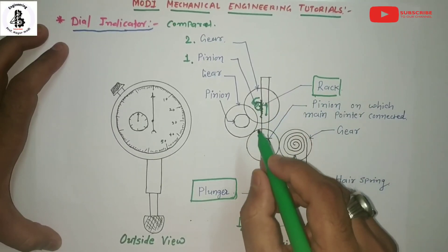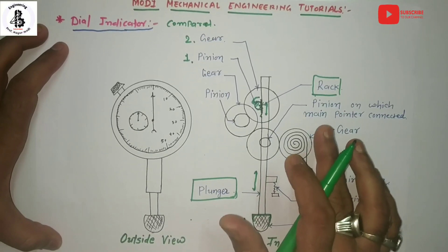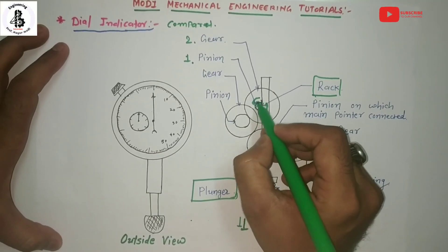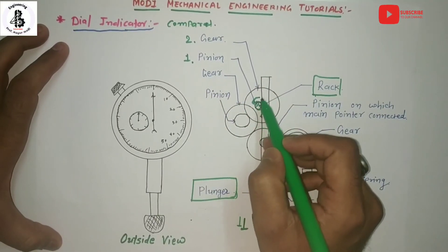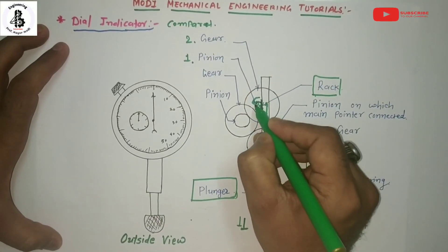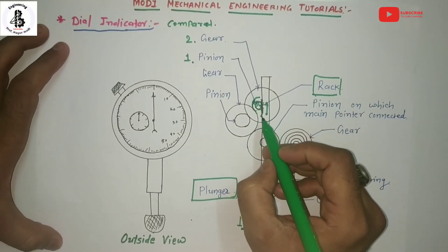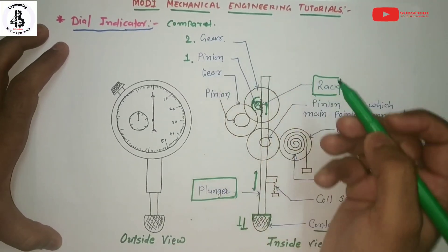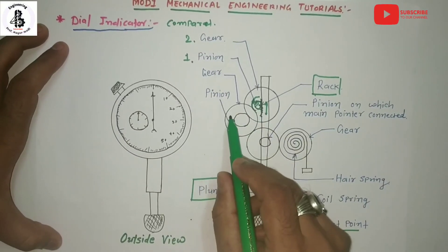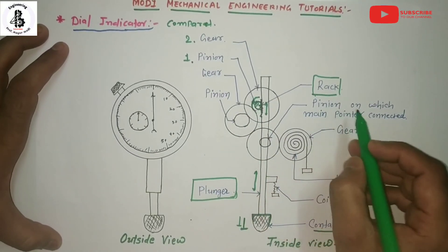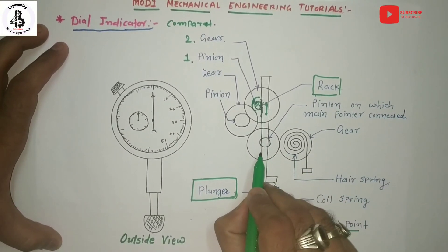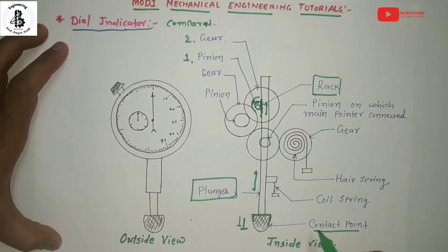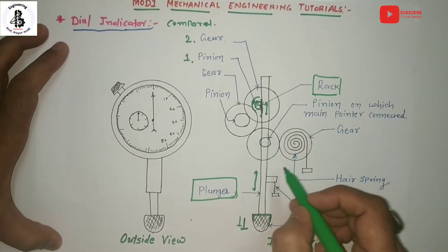This is the basic mechanical concept used for the indication — reciprocating motion is converted into rotary motion. First, through the pinion connected to the gear, this pinion and gear rotate. That gear and pinion mechanism is once again connected to another pinion-gear mechanism. One more pinion-gear mechanism connects to the pinion on which the main pointer is attached. So by the up and down movement of the contact point, all these components rotate according to their connectivity.